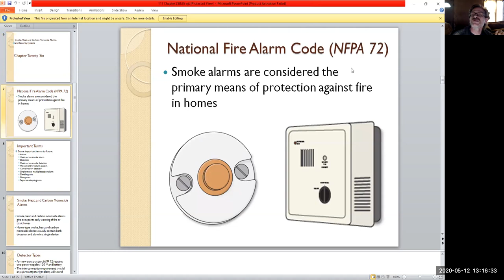Then they go through important terms you should be familiar with, like what a heat versus a smoke alarm is. They're different types of detectors - one detects heat, one detects smoke, and usually they're built as a dual that detects both. Generally you want it to detect smoke, since you usually get smoke before heat, but in some cases the smoke might get ventilated while a fire is still occurring, so you'd want a heat detector as backup.